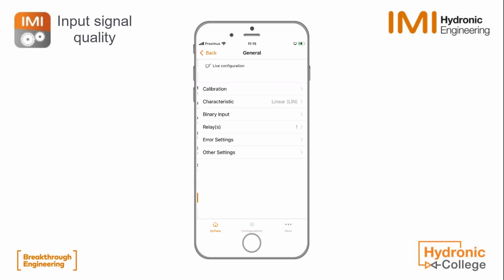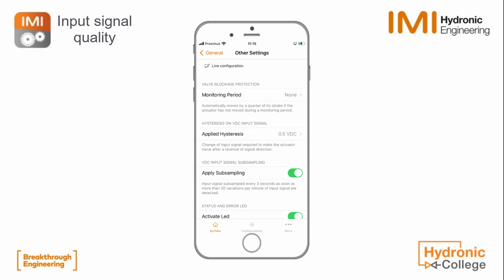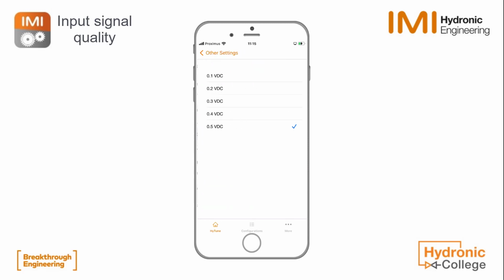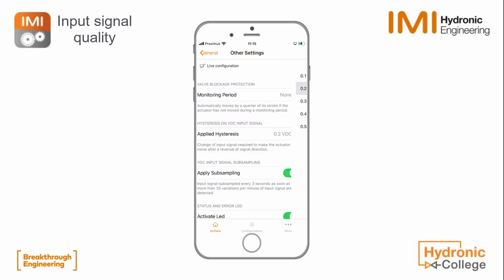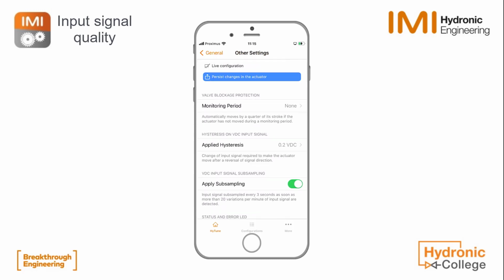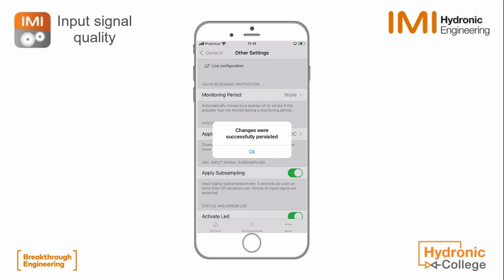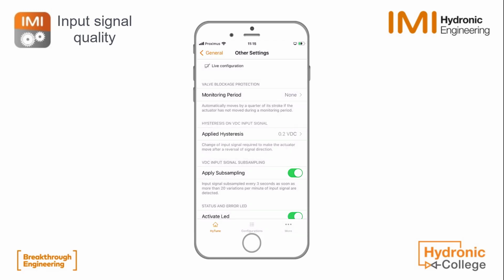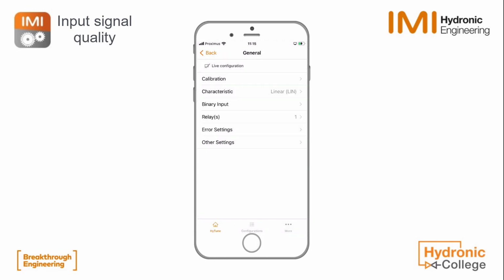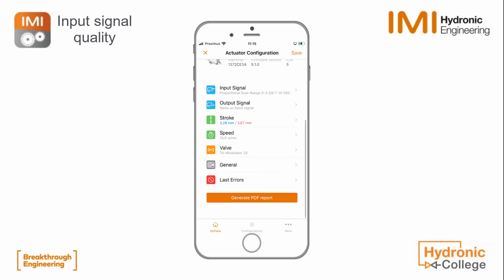So when we click via general to other settings, we can set the applied hysteresis. In this case we have 0.5 volts DC. The factory setting is 0.2 volts. So when we change this here, this could be useful for fluctuations or to filter out some big fluctuations in the input signal line.